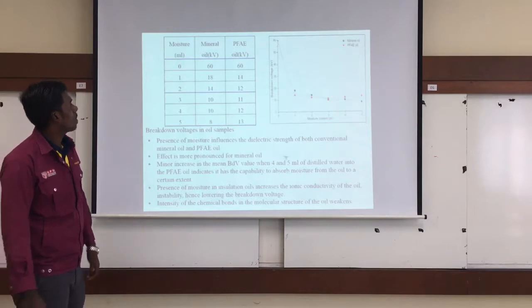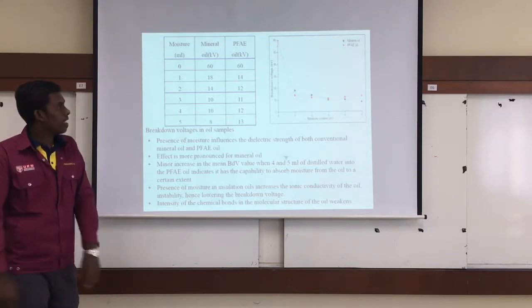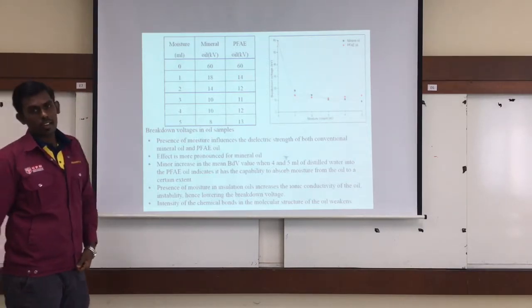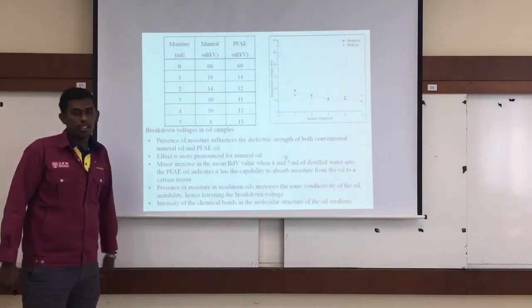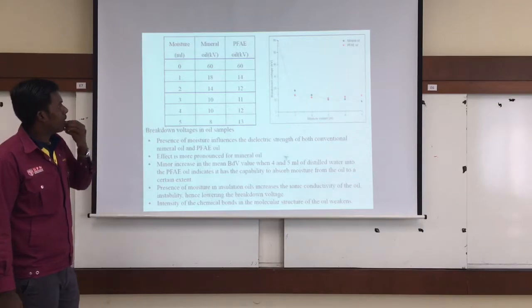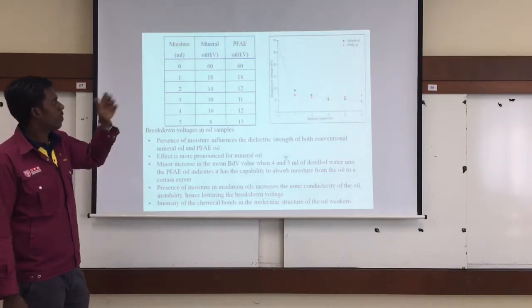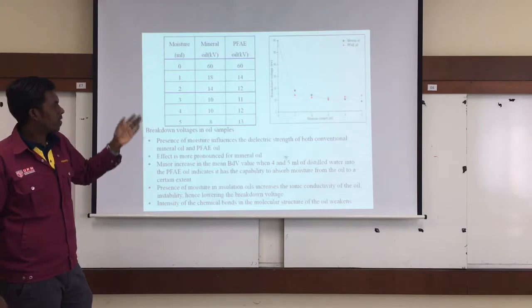As you can see, this is a comparison between mineral oil and PFAE. When we add a certain amount of moisture, for example from 0 to 5 ml, you can see the breakdown strength of the mineral oil and the palm fatty acid ester oil is decreasing.